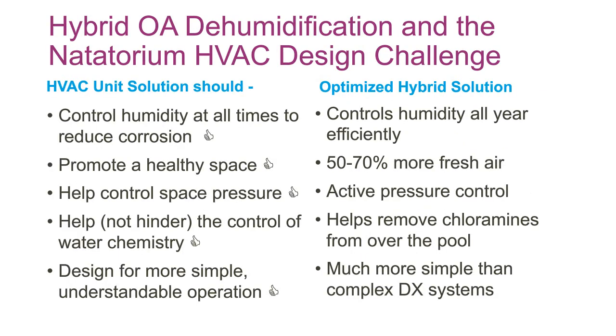So if I go back to the sort of design challenge that I mentioned when we got into the market, using this optimized solution controls the humidity all year round, so that should control the corrosion. We're getting typically 50 to 70% more fresh air. In some cases, it's even higher than that if they were using a lower percentage to start. So a lot more outside air to the space. The system has an active pressure control that moves with the change in ventilation air, and that works very well.